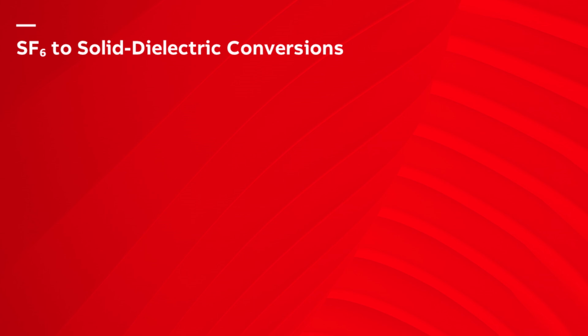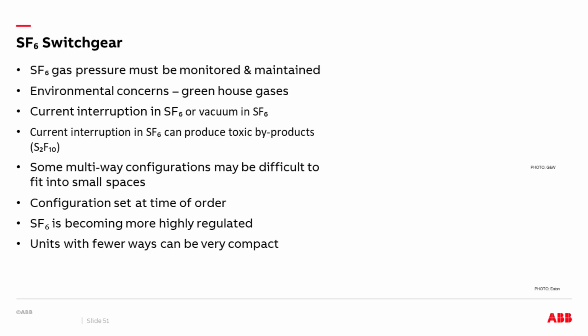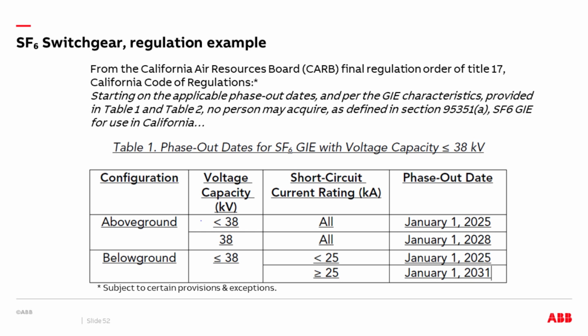Now on to SF6, unless there's a question. Okay, so SF6 has been, again, another insulation material that's been around a long time, very successful. It's used extensively in substation breakers. Unfortunately, it's a greenhouse gas, and some states are moving to eliminate it or minimize its use in new installations. There are a number of issues around SF6 byproducts if there's arcing in SF6. Sometimes it's difficult to configure in small spaces for multi-way configurations. It's becoming more regulated, so this drives some utilities to have a program to want to consider replacement.